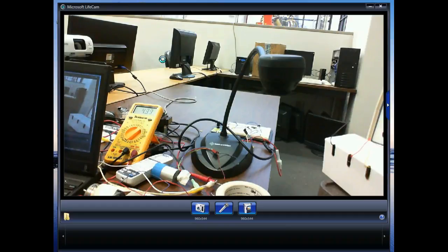Just about all PLCs have what they call a high-speed counter. So I could bring the output of this thing into a high-speed counter. That sucker has no problem with the speed of the motor. So we could put 32, 40 notches on our encoder, to get a real high resolution. Now we can count it over a shorter amount of time. That's all.